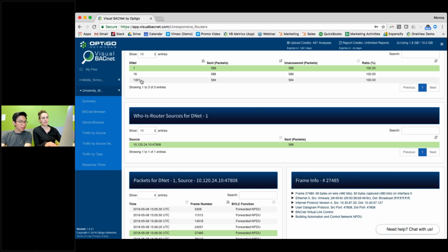Hey, Daniel, answer me this. If this is a BBMD network that it's looking for and the network's on the other side of the BBMD, this is potentially an IT problem, would it not be? An IT problem. It is on the other side of the BBMD. But it would be broadcasted. The who-is-router-to-network and I-am-router-to-network should be broadcasted. So if the IP network is set up correctly, it should reach all of the routers.